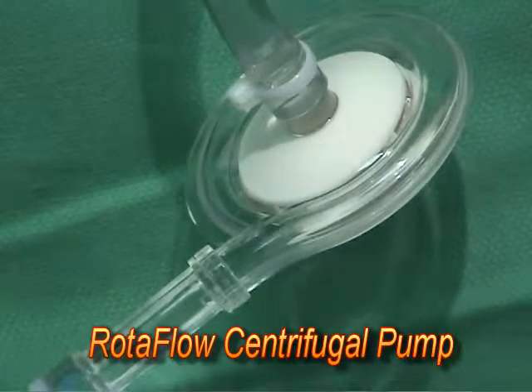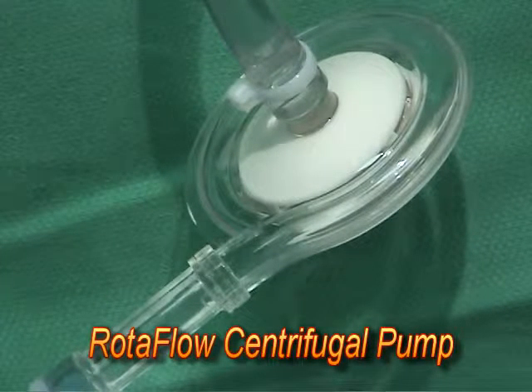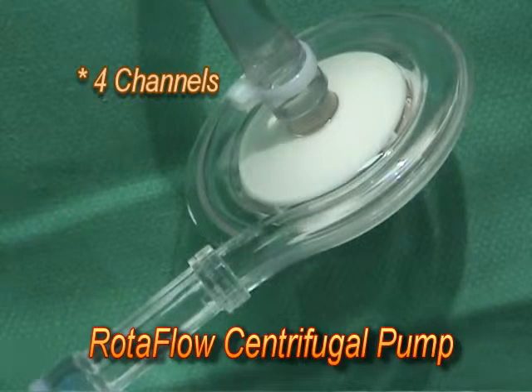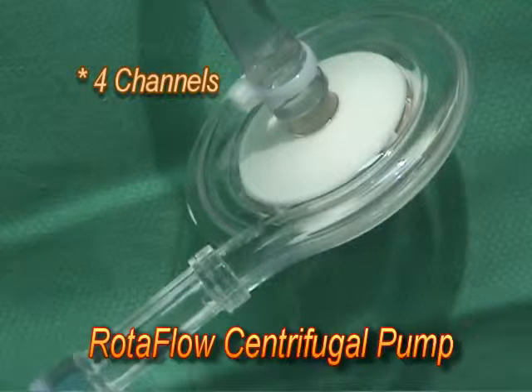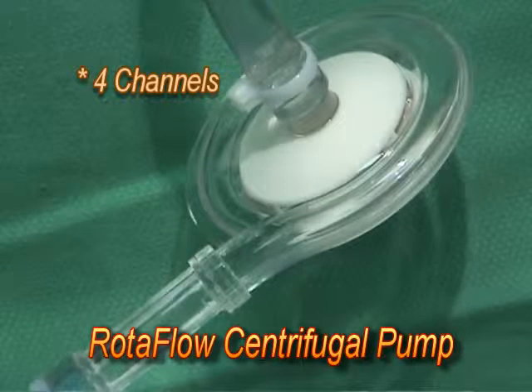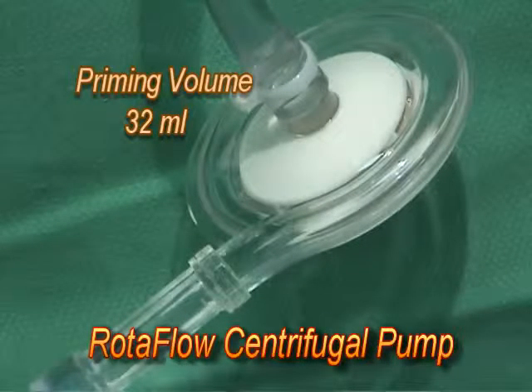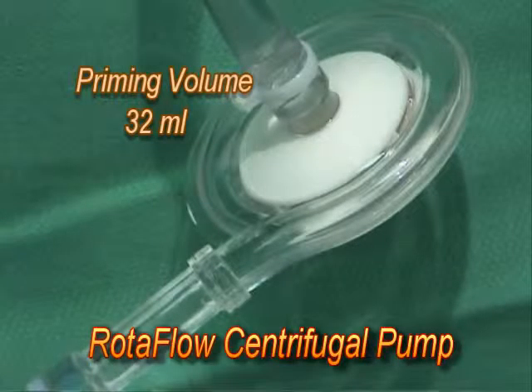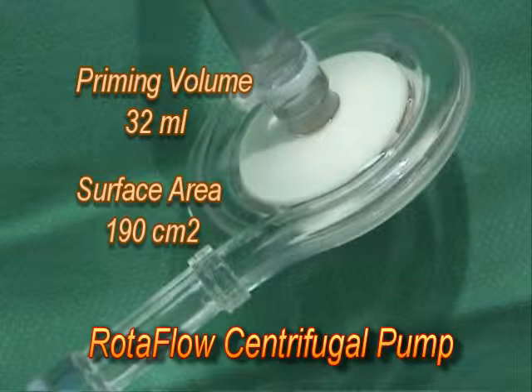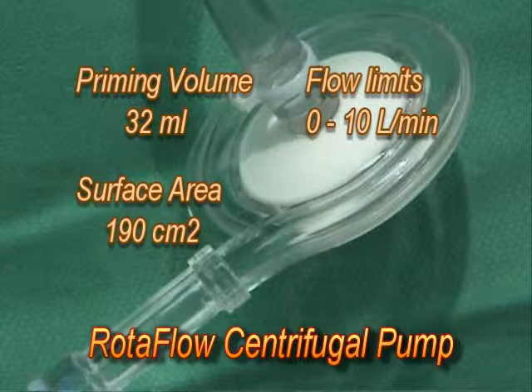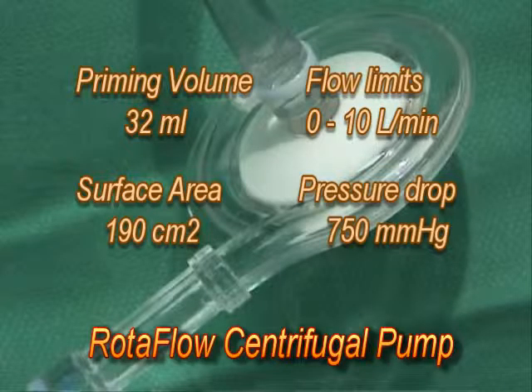The RotaFlow centrifugal pump has a spinning rotor with 4 flow channels, which imparts rotary motion to the incoming blood, directing it through a spiral housing to the outflow port. The priming volume of this pump is 32 milliliters, and it has a surface area of 190 centimeters squared. The flow limits are 0 to 10 liters per minute, with a maximum recommended pressure drop of 750 millimeters of mercury. This pump has 3/8 inch inlet and outlet ports.